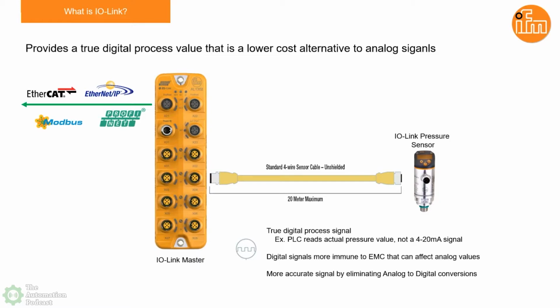The big thing is, why don't we use more analog signals on our processes? Usually it's because there's a significant cost adder when adding analog back into a system. So in many cases, because that cost adder is too much, we default back to just taking an on-off signal because it's the cheapest way to run the machine or process. But imagine being able to get more granular information from your sensor into the PLC without that cost adder.